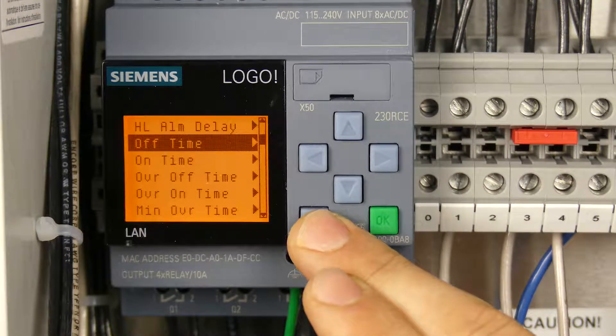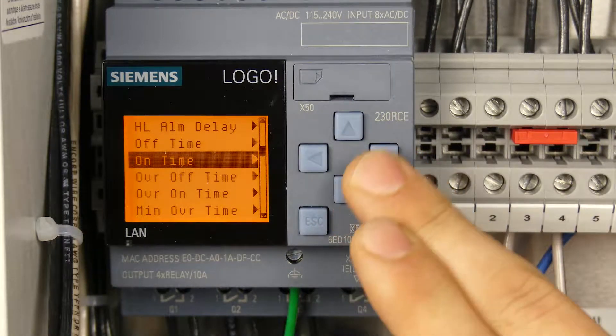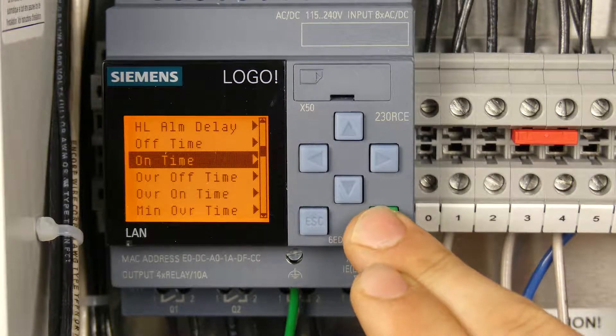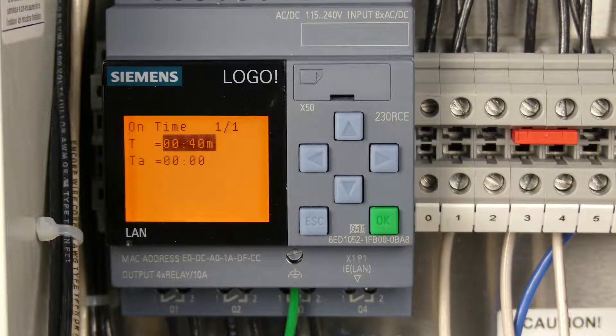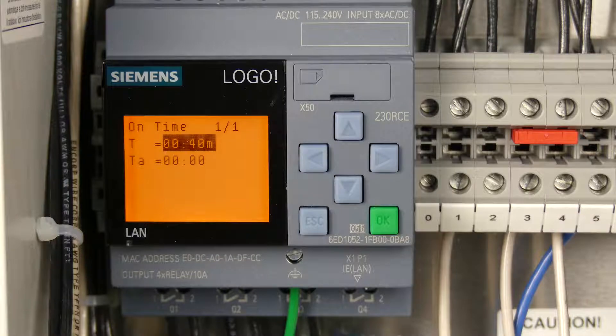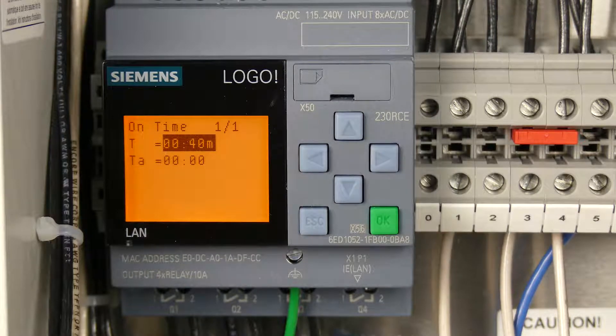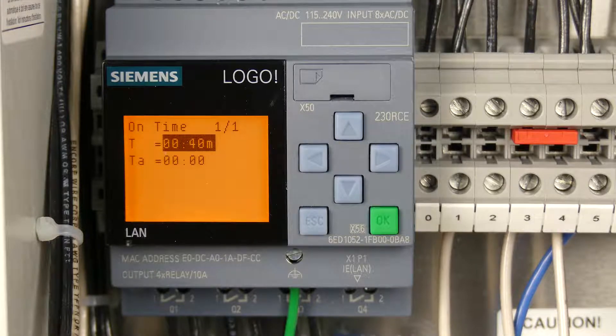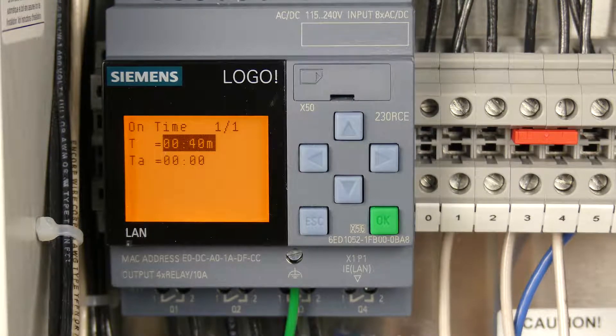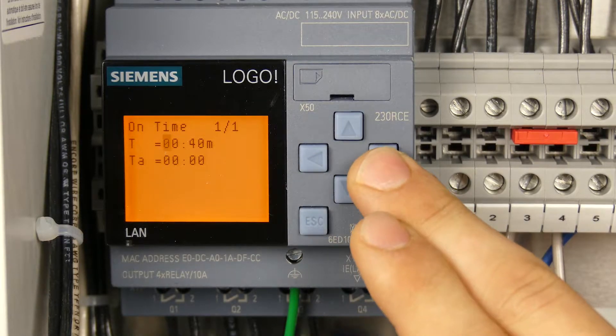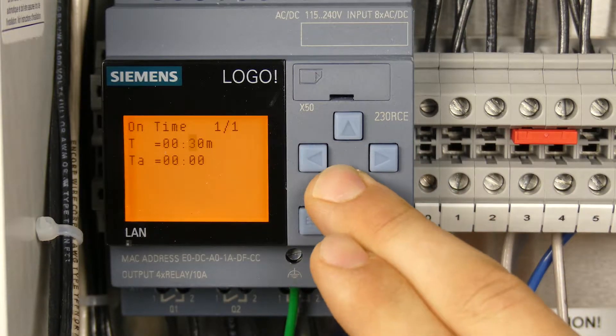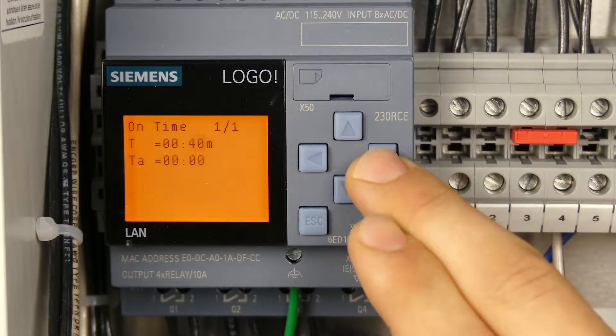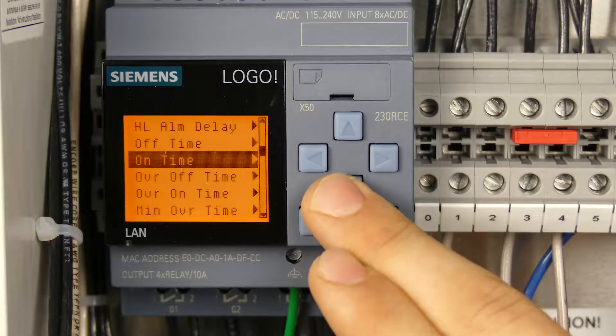Let's move to on time, which works right alongside the off time. On time is your pump run time, and this is important to calculate exactly how much volume you're dosing for every dose. Depending on how much flow your pump has and how much you need to dose on each cycle, you're going to adjust this parameter just like the other ones. Press OK to edit, go over and adjust your time up or down. Again, you can adjust minutes, hours, or seconds.